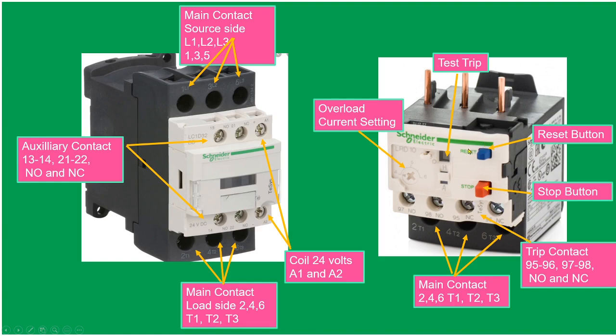The next one is the overload relay. The overload relay here has overload current setting. If we are going to increase the current, we can adjust this one using a screwdriver. Test trip: if we're going to try to test the overload to see if it's working or not, we just push this one. This one is the reset button. If our overload trips, we're going to reset this one after a few minutes. If we're going to stop the motor, we can also press this red button and the motor will stop.